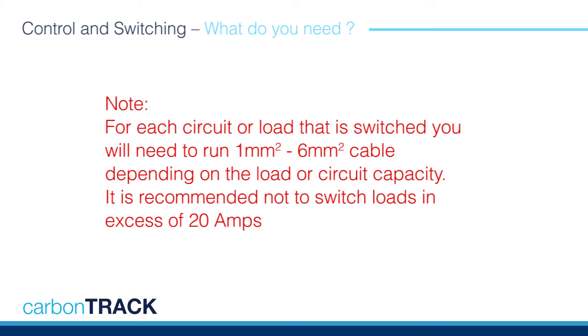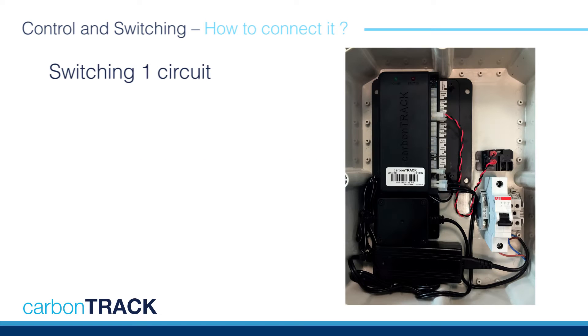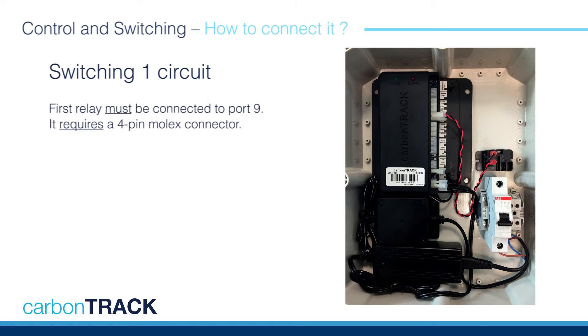It is recommended not to switch loads in excess of 20 amps. The CT100i switching ports must be populated in ascending order.